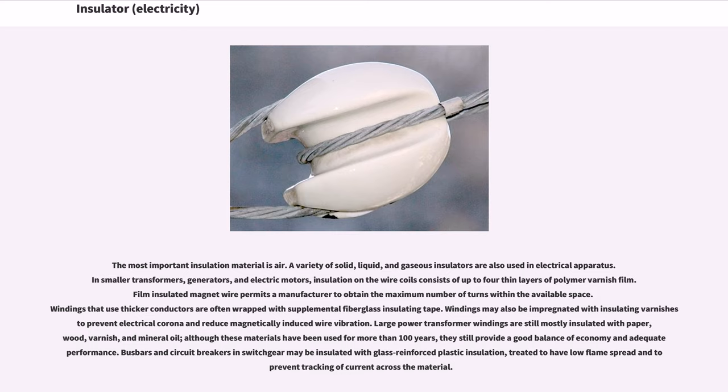A variety of solid, liquid, and gaseous insulators are also used in electrical apparatus. In smaller transformers, generators, and electric motors, insulation on the wire coils consists of up to four thin layers of polymer varnish film. Film-insulated magnet wire permits a manufacturer to obtain the maximum number of turns within the available space. Windings that use thicker conductors are often wrapped with supplemental fiberglass insulating tape. Windings may also be impregnated with insulating varnish to prevent electrical corona and reduce magnetically induced wire vibration.